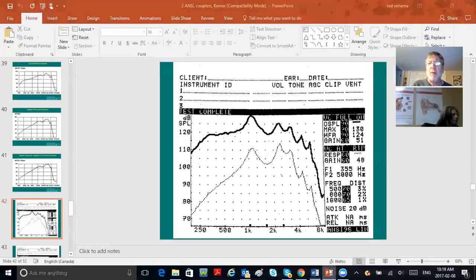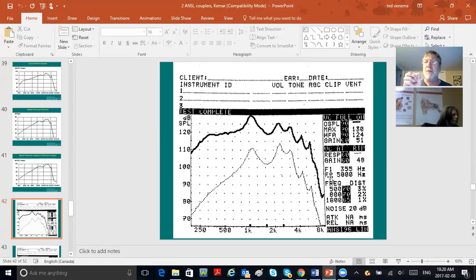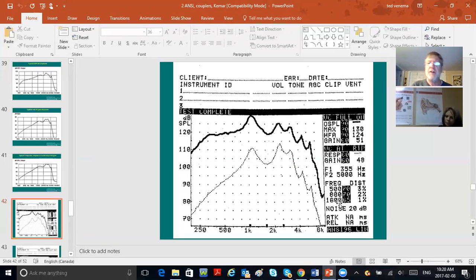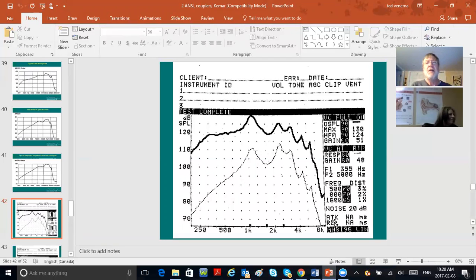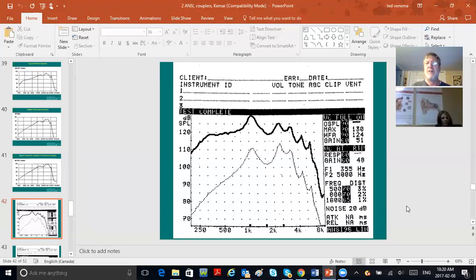On the ANSI display, you'll see frequency distortion at 500, 800, and 1600 Hz—ignore the F1 and F2 values, those concern the breadth of frequency response and are mostly for the manufacturer. You'll also see equivalent input noise—in this example 20 dB, which is good. Those are the five main ANSI tests: OSPL 90, full-on gain, reference test gain, equivalent input noise, and harmonic distortion. There are also attack time and release time, but we don't really care about those as much.